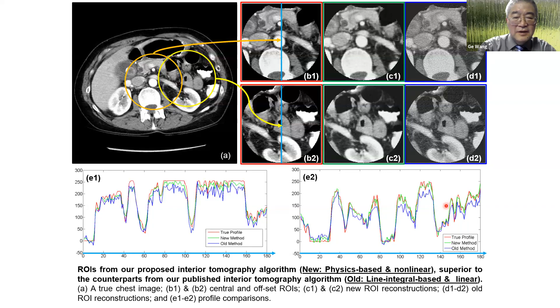So this is what we have been pushing forward. With interior tomography, as I mentioned earlier, we could use 3 X-ray tubes to perform triple-source helical cone beam scanning. Now with interior tomography, we can put in more X-ray source points, a larger number of X-ray tubes, with a smaller field of view and a smaller detector panel. Otherwise, you do not have space to fit into a donut-shaped gantry. So with interior tomography, we can indeed target a small region of interest, like a plaque in your heart, or a stent you want to characterize.